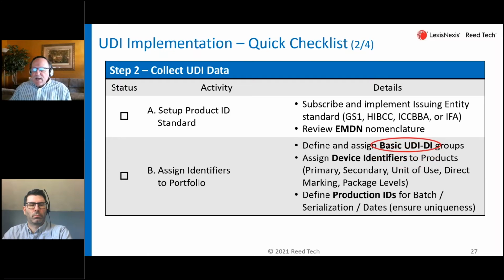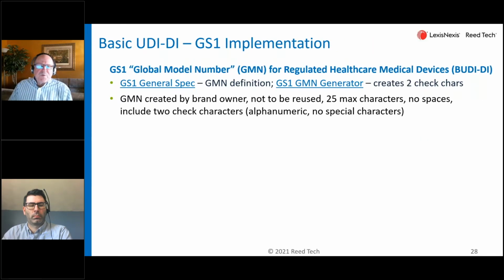We do get a lot of questions about the new concept that the European Union has called a basic UDI-DI. And this was not present in the FDA, so there's no background that you can point to and say, oh, this is how we did it before. No, this is a brand new activity. So a couple things about the basic UDI, and just for discussion purposes, I'm going to use the GS1 implementation.